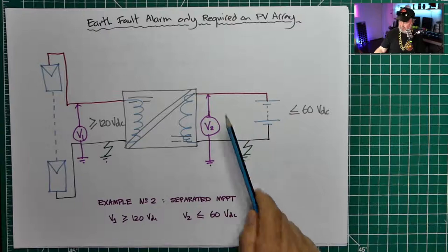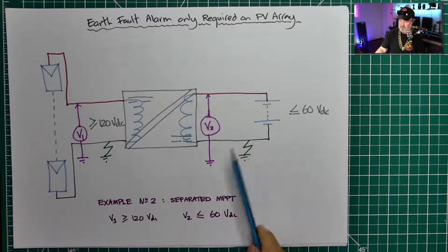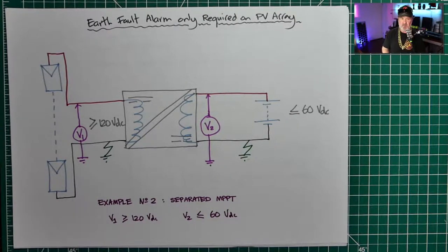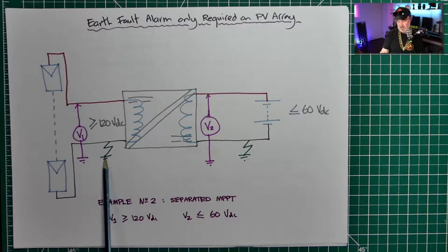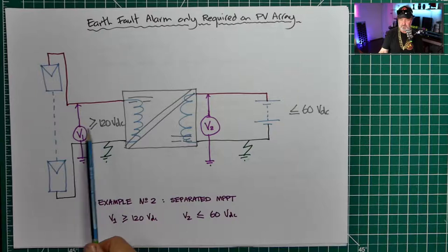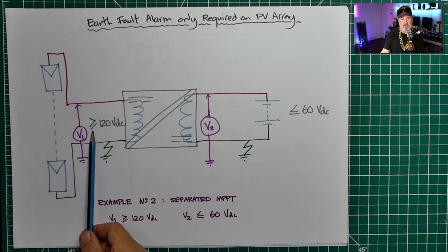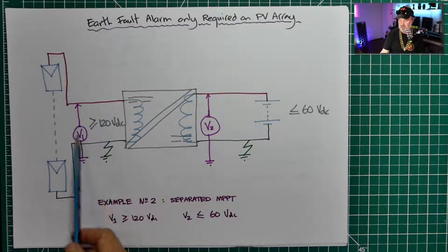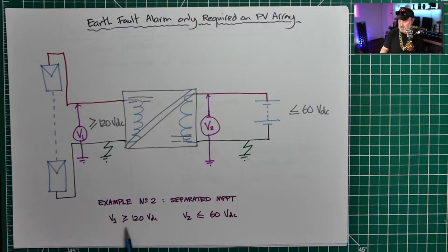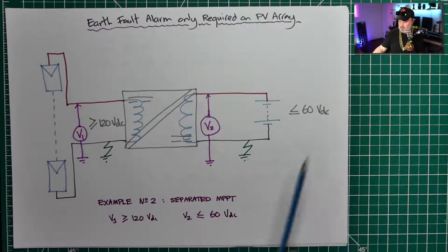We'd only see the maximum voltage of the battery. But on the PV array side, we still have an HV PV array. An earth fault on that side, if it's over 120 volts, we're required to have earth fault detection on the PV array side. So we've got to detect that earth fault at V1 — which could be up to 120 volts or above — whereas V2 is going to be at the battery voltage.